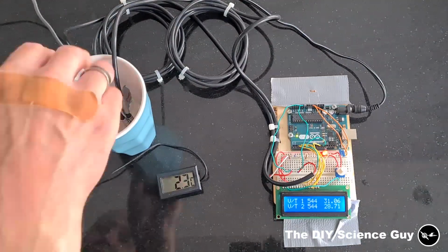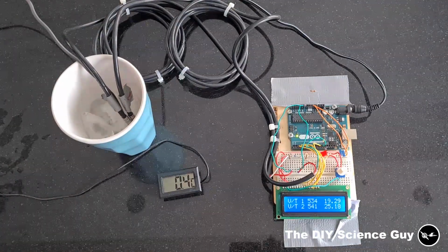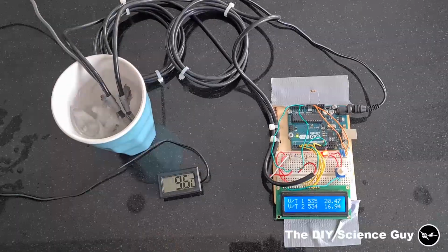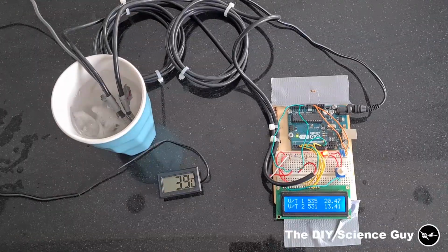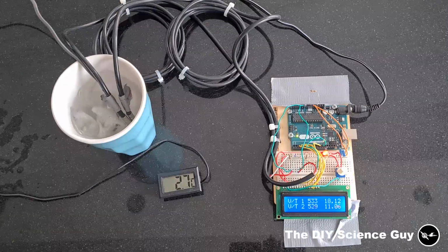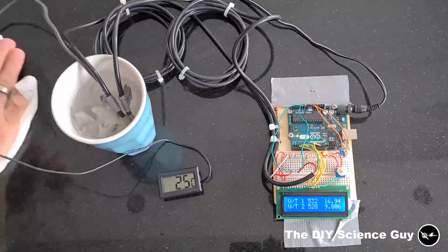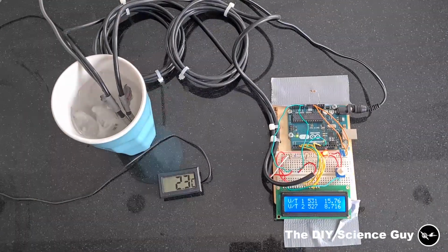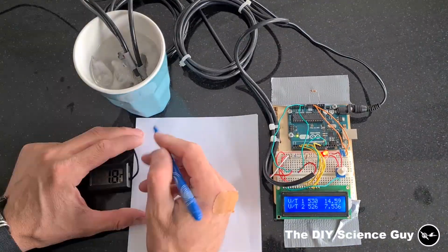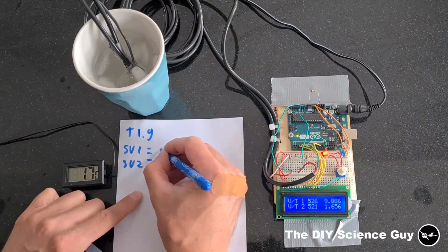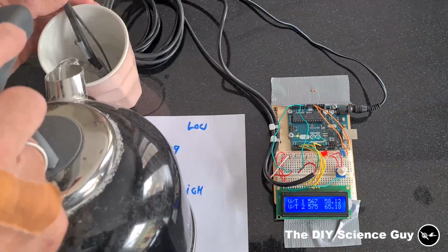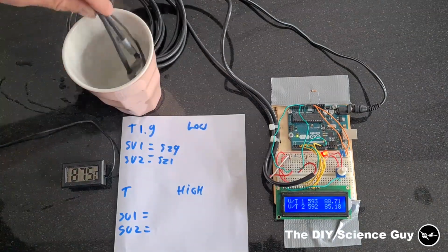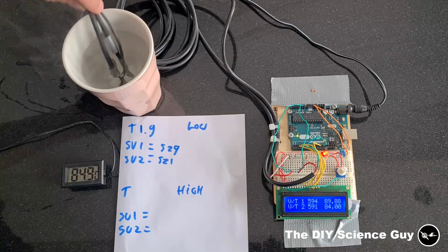To do the calibration, you take a cup of water with ice in it to get the temperature as low as possible, and use a separate thermometer that is reasonably accurate, depending on your needs, to measure the water temperature. Then put the PT100 in the water and write down the sensor value and the water temperature. Then do the same thing with hot water and also write down the sensor value and the water temperature.